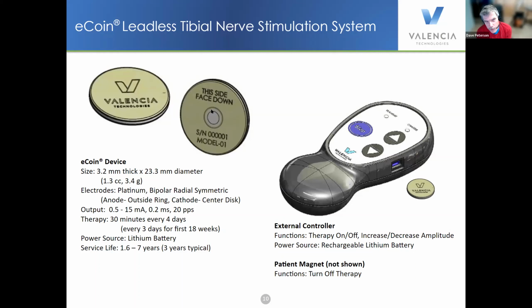Well, it lets us put a really tiny magnet sensor inside the implant. If you're talking about an RF or any kind of antenna system, you've got to at least have an antenna, and then you've got to have the demodulation circuitry and so forth for that. And even if you do a tremendous job of that, the volume of that can be considerable. Well, a magnetic sensor only takes about a cubic millimeter in your device. There's just not many communication systems that can do that. So I thought that, in terms of a neat way to use sort of old technology, that was kind of a neat thing we did here.